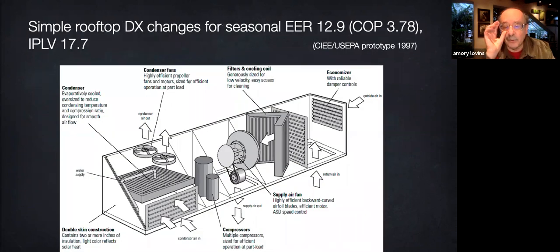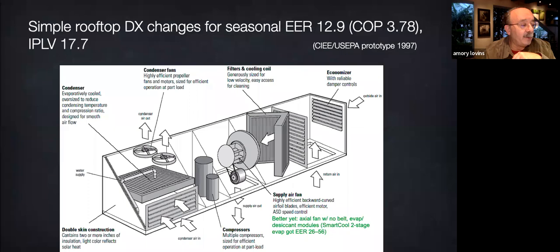And putting together even more good stuff in a standard rooftop box could do even better. That was prototyped 24 years ago. In fact, it could be further improved with a direct drive axial fan rather than the belt-driven fan you see there, and with added evaporative and desiccant modules. Today's best units actually have an integrated efficiency metric, which is now called IEER, upwards of 21, but two-stage evap has demonstrated 26 to 56, and regular maintenance is essential too. As with much equipment, a bad unit, well maintained, will often outperform a good unit, badly maintained.